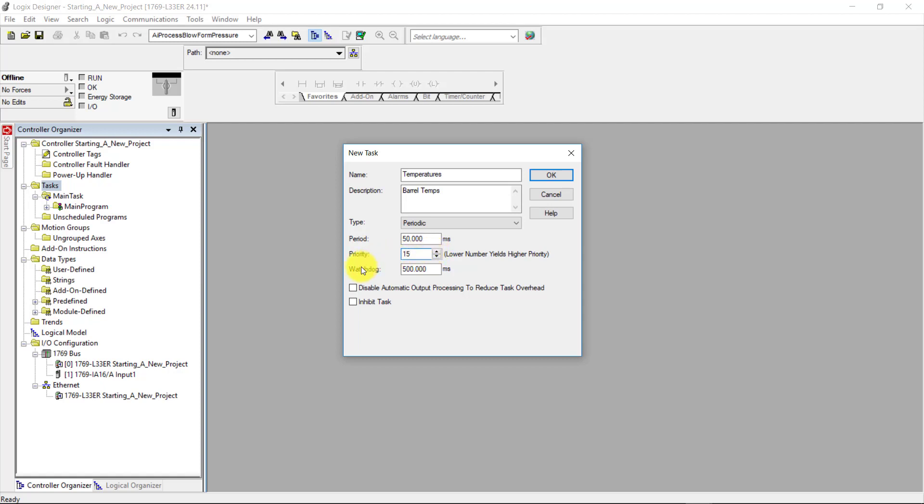Next is the watchdog. The watchdog I'm going to leave at 500 milliseconds for right now. So next, I'm going to come down here to the disable automatic output processing to reduce task overhead, and I'm going to leave that unchecked. And I am also going to leave unchecked the inhibit task because I want the task to run.